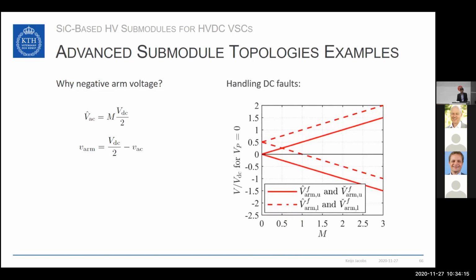Another point here is handling DC faults. In this case, I plotted the same curves for a case of a pole-to-ground fault on the positive pole. As you can see here, even running the converter at a modulation index lower than 1, we need negative arm voltage.